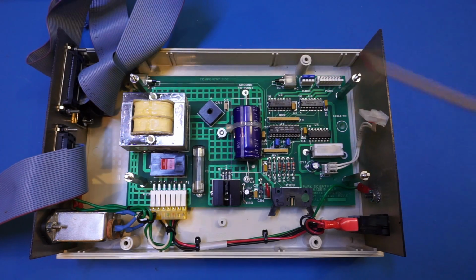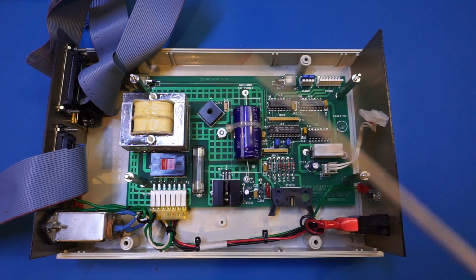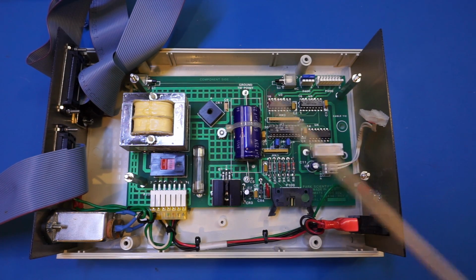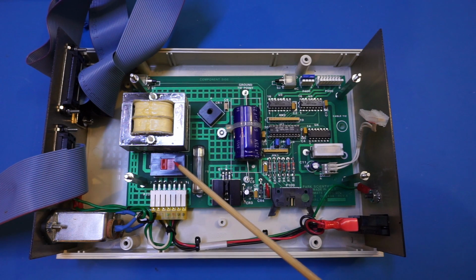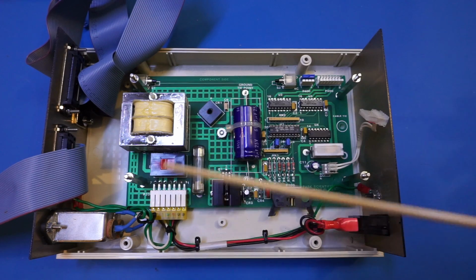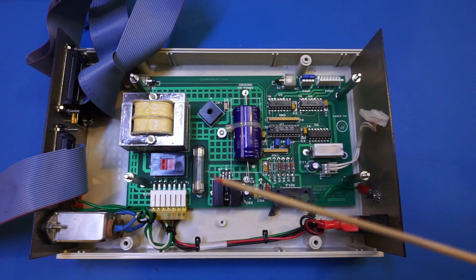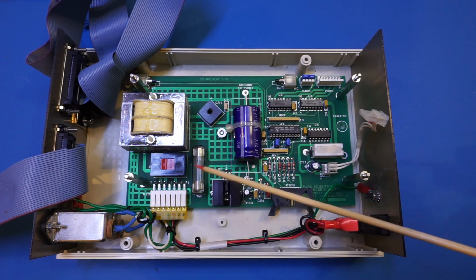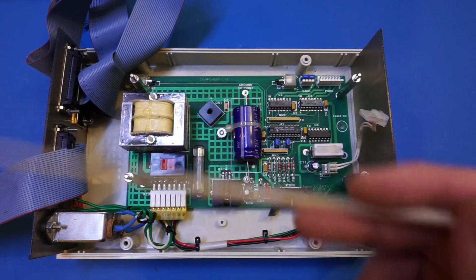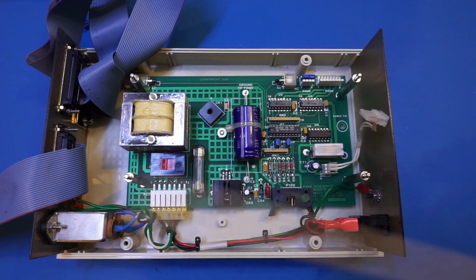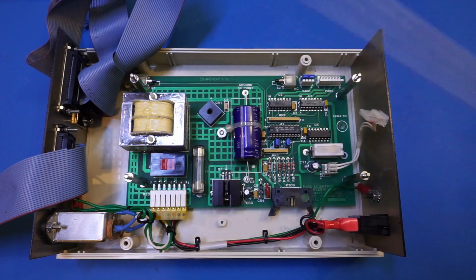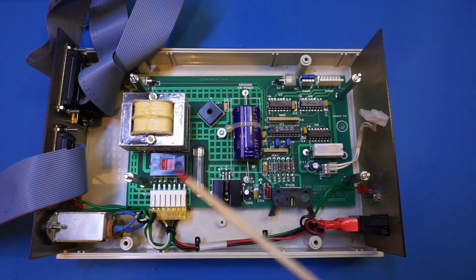And here is the PCB at the bottom, and not surprisingly, there's not too much going on on this board. One thing interesting is that they have this 115 volts and 240 volts voltage selection switch mounted right on the board instead of on the rear panel, which means if you need to switch the voltage for whatever reason, you have to open the unit up and disassemble it to this level and do the switch. And similarly with this fuse mounted right on this board inside this unit, if for any reason you need to replace the fuse, you have to do the same exercise. But other than that, no complaints here.